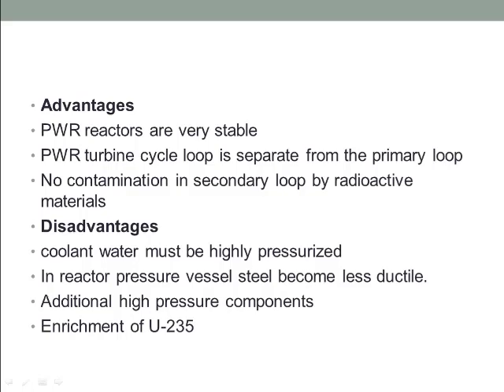Some disadvantages are also associated with the pressurized water reactor. The coolant water must be highly pressurized to remain liquid at high temperatures, requiring high-strength piping and heavy pressure vessels, which increases the construction cost. The higher pressure can also increase the consequences of a loss-of-coolant accident. Additionally, the reactor pressure vessel is manufactured from ductile steel, but neutron flux from the reactor causes the steel to become less ductile over time; eventually the ductility reaches a limit determined by applicable boiler and pressure vessel codes, requiring repair or replacement. Additional high-pressure components such as reactor coolant pumps, pressurizer, and steam generator are also needed, further increasing cost.